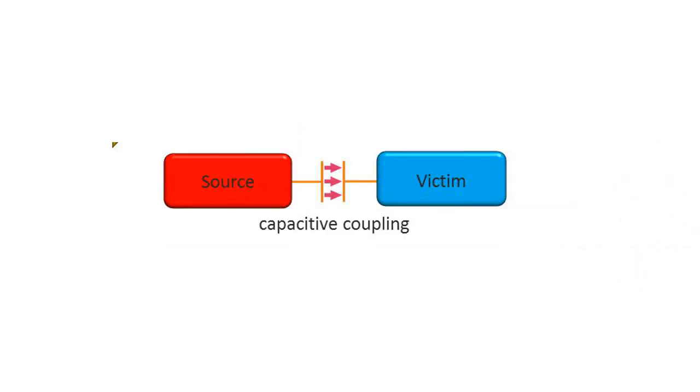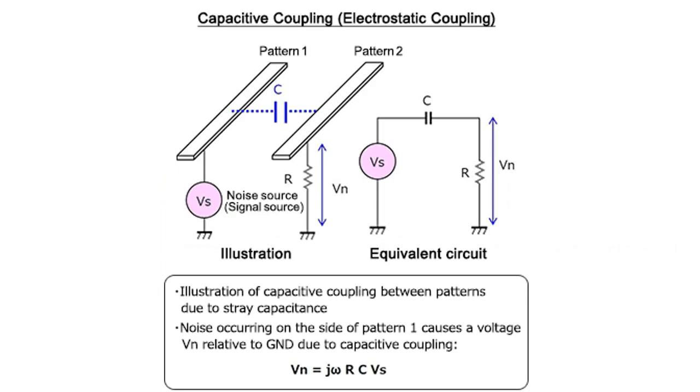Second is capacitive coupling, which can happen when two cables of the system are routed close to each other, thus forming a parasitic capacitor. Capacitive coupling is typical for industrial applications where power and signal lines are laid parallel over long distances.